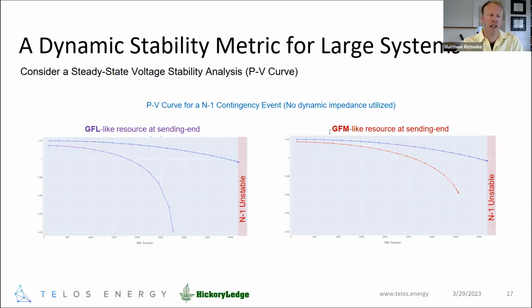Voltage declines much more quickly. Unlike with a grid-forming-like resource at the sending end—so just making that substitution and rerunning the PV analysis—you see that the grid-forming-like resource provides much better voltage support, and actually enables the system to transfer more active power out of the sending end relative to the grid-following-like resource. The big difference here is how well each of these resources supports the voltage.